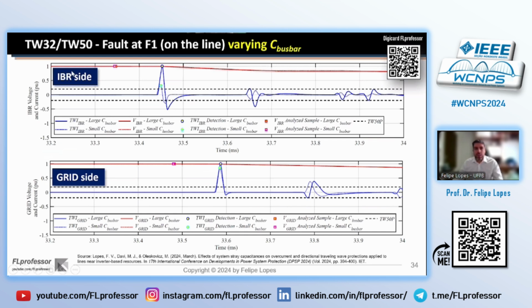Just to demonstrate here the directional and overcurrent elements, here we are comparing the current traveling wave with the voltage sample. For internal fault here, we can see that the elements operated properly, but varying the stray capacitance, depending on the threshold that is chosen, we can have some difficulties in properly detecting this wave here. On the other hand, on the grid side, the waves are very strong and no problems are verified. Actually, we didn't see problem here, but we could see a possible problem that could occur if I choose a higher threshold.